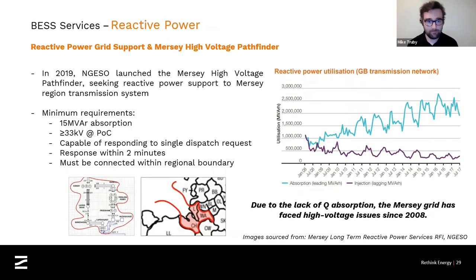Next slide, please, Sam. The Mersey region has historically, over the last 15 years, had a particular issue around high voltage and reactive power imbalance. What they've been seeing is that the amount of reactive power on the system that needs absorbing has been rising disproportionately to the rate that can be absorbed. To manage the high voltage issues that they were facing as a result, in 2019 National Grid launched what they called the Mersey High Voltage Pathfinder, which was a competitive procurement exercise to get services from generators that could help to manage reactive power.